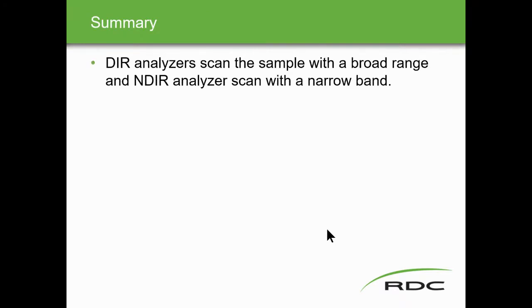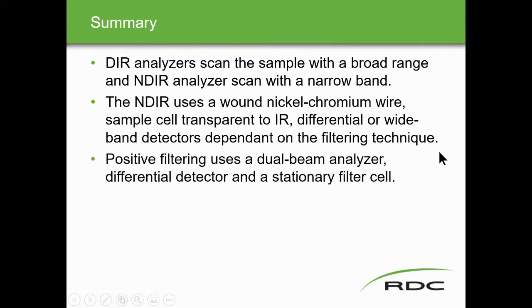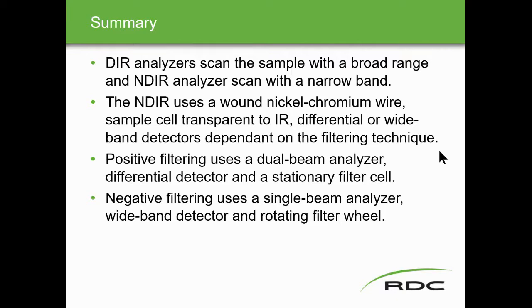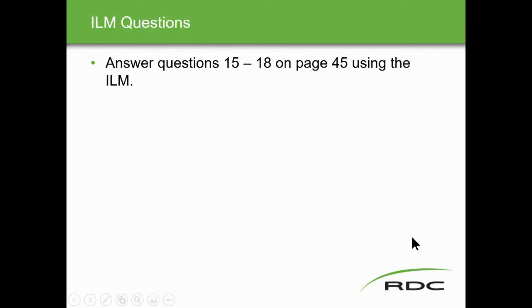Summary: DIR analyzers scan the sample with a broad range of IR wavelengths; NDIR analyzers scan a narrow band. Non-dispersed IR uses a wound nickel-chromium wire source and sample cells transparent to IR. Differential or wideband detectors are used depending on the filter technique. Positive filtering uses a dual beam analyzer with a differential detector and stationary filter cell. Negative filtering uses a single beam analyzer with a wideband detector and a rotating filter wheel. IR analyzers can be used on samples extracted from the stack or in-situ (open path).